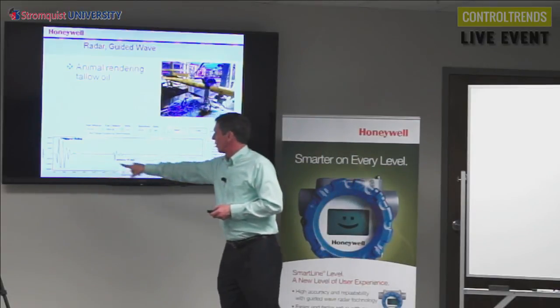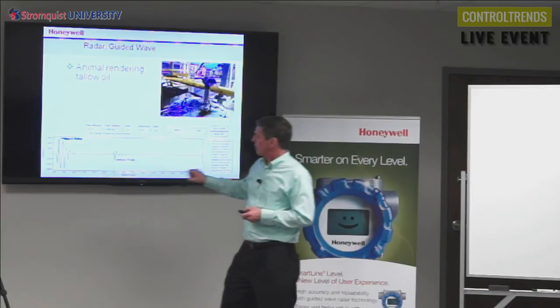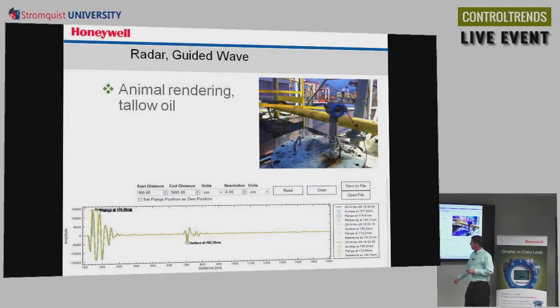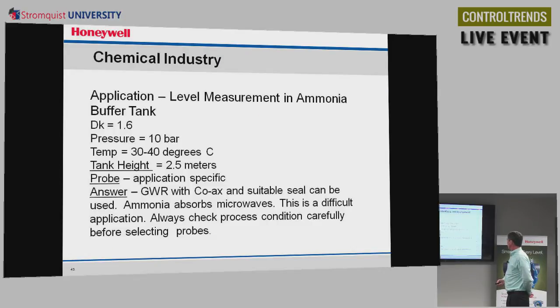And here's a look at an echo curve. This is actually the output from there. This is the flange reflection and then the reflection at the surface. So not a common application, but that's one that works. I'm going to take a quick look at this ammonia application, just to say that ammonia is something that we can do, but it's one that we want to approach with caution. It has a low dielectric, and ammonia is just tricky in general, I think really because it absorbs some of the microwave energy. So it's something we can do. It's probably not something we'd want to do for a really long measurement range, but looking at the application, it's something we would consider.